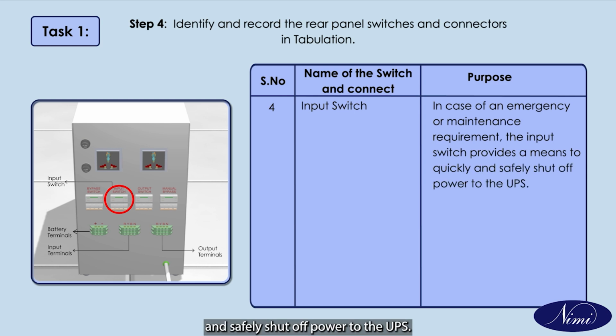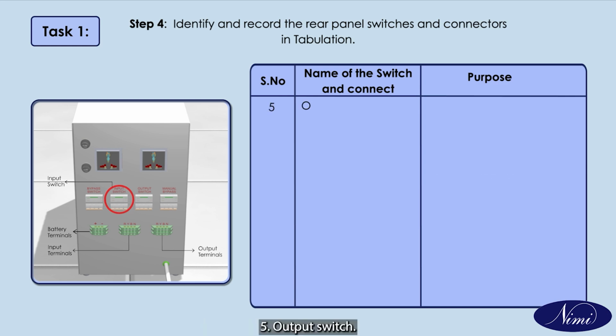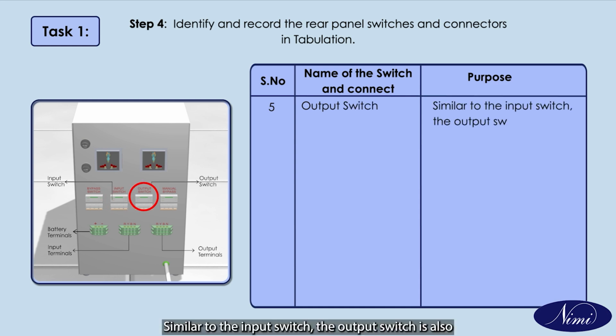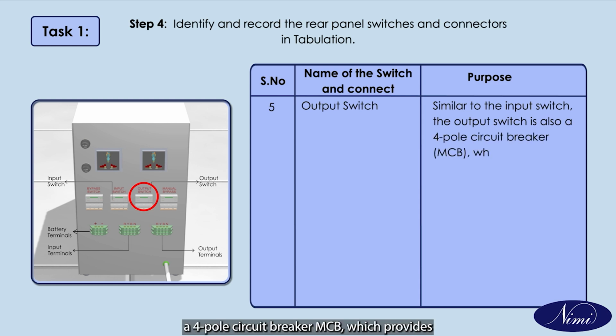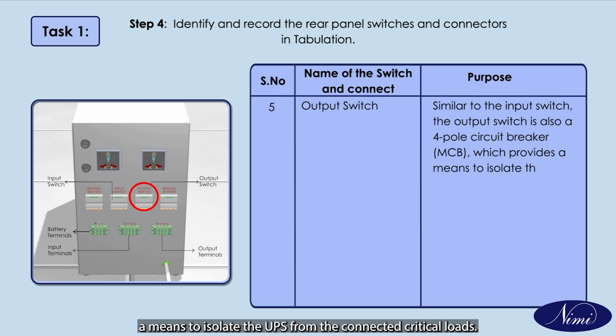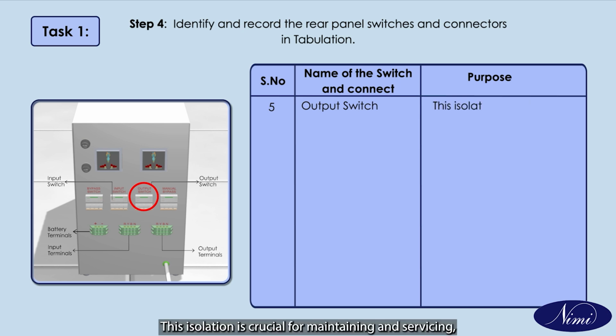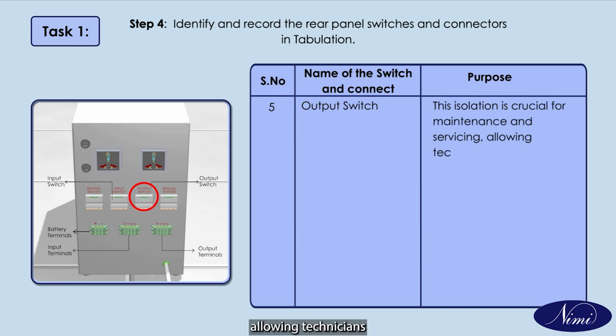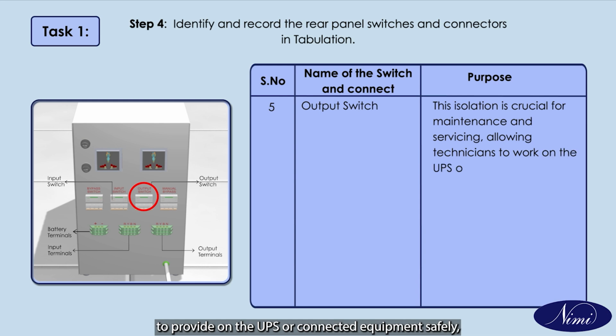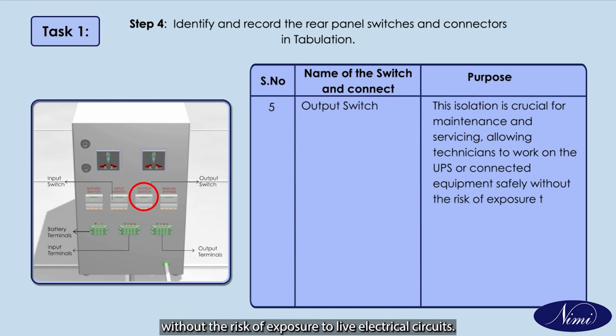In case of an emergency or maintenance requirement, the input switch provides a means to quickly and safely shut off power to the UPS. Number 5. Output switch. Similar to the input switch, the output switch is also a 4-pole circuit breaker MCB, which provides a means to isolate the UPS from the connected critical loads. This isolation is crucial for maintenance and servicing, allowing technicians to work on the UPS or connected equipment safely without the risk of exposure to live electrical circuits.